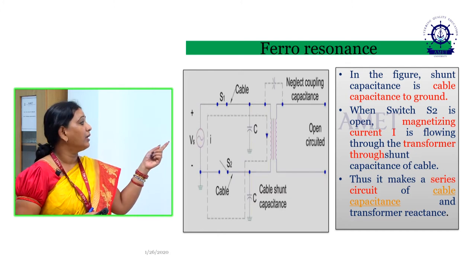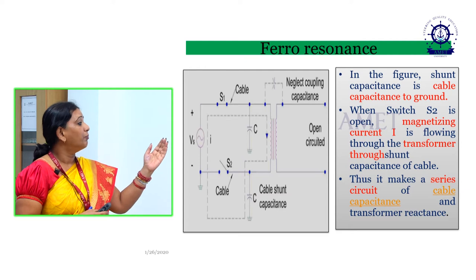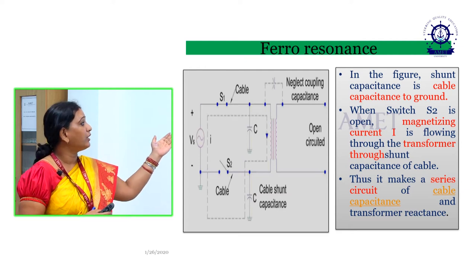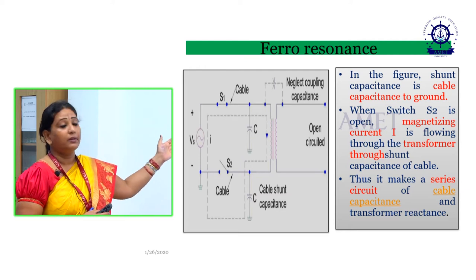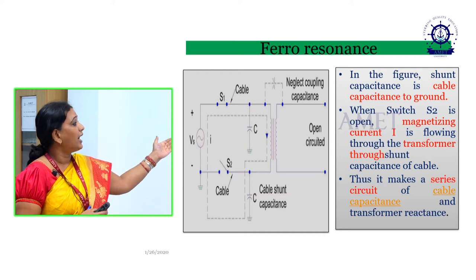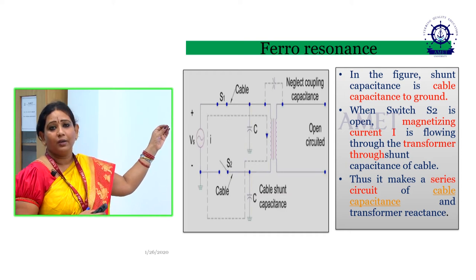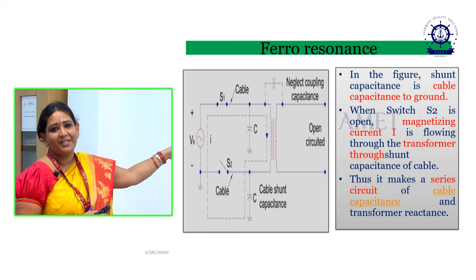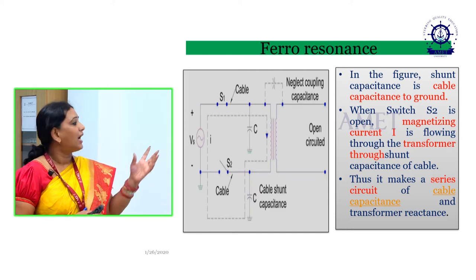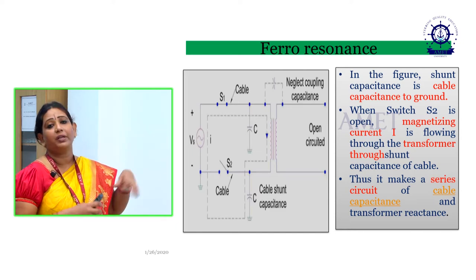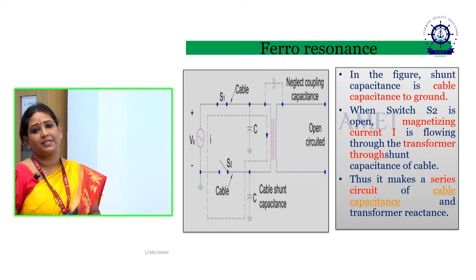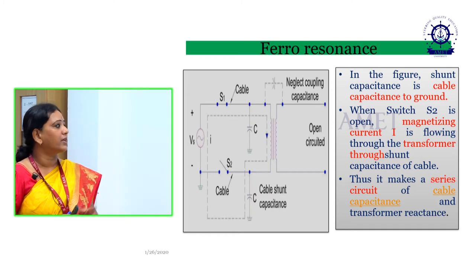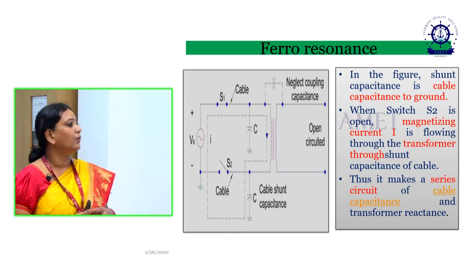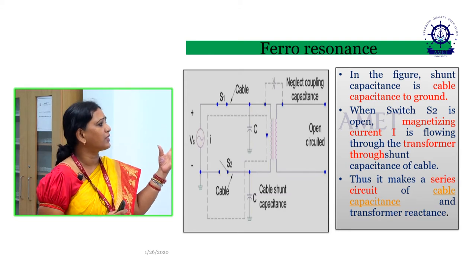That current, upon closing, may flow in a backward direction and go into the input side, and it creates an over voltage in the system voltage. So system voltages get interrupted, and this over voltage will affect whatever components are connected into the system. This condition is called ferroresonance, and this has to be overcome.